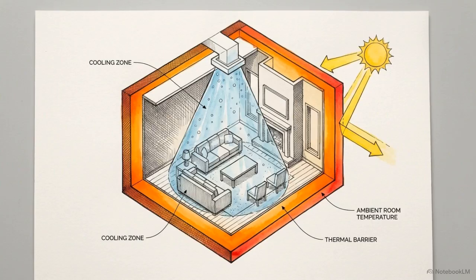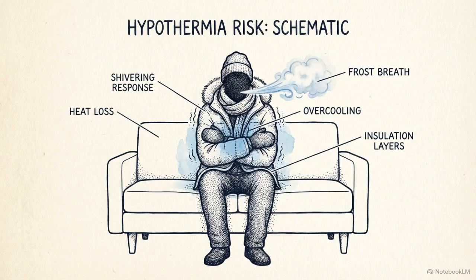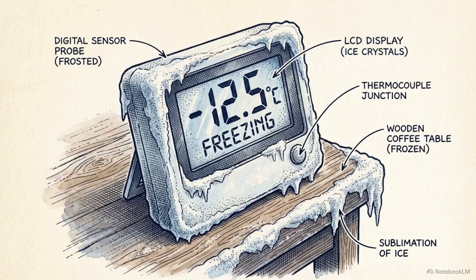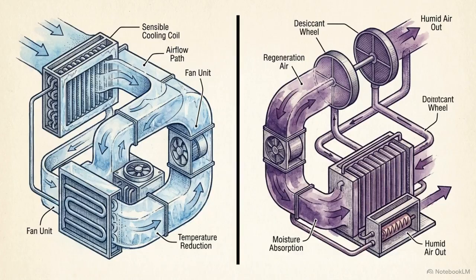That 15 degrees supply air is then pumped into a space that has almost zero external heat penetrating the walls to offset it. The occupant experiences the overcooling trap. The absolute humidity reaches the correct level, but the room becomes freezing and thermally uninhabitable. Successfully reaching the humidity target using pure sensible cooling breaks the thermal comfort requirement entirely. To solve this, sensible cooling and latent dehumidification must be mechanically decoupled.